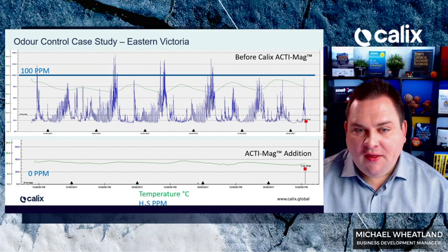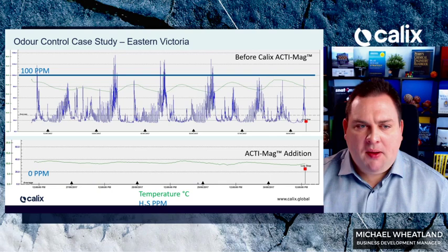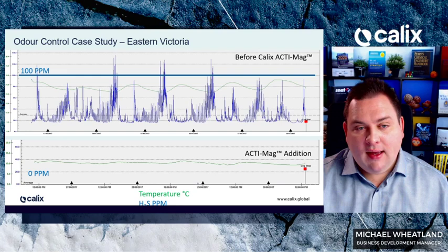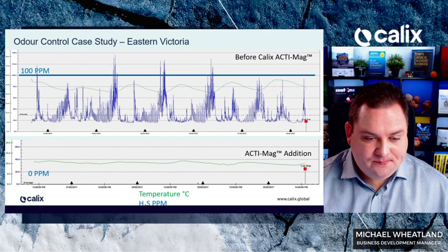But this was maintained for quite a long time. The reason I've only displayed a week is because it's easier to see. We did see after about 3 weeks there was a power failure there, and we saw the hydrogen sulfide pop back up again, and then we turned the system back on and it came back down. So it's able to maintain it on an ongoing basis.